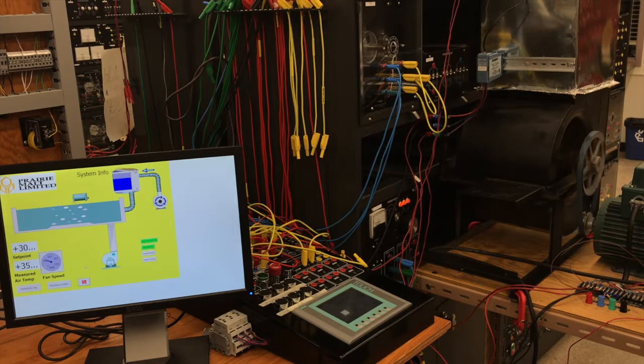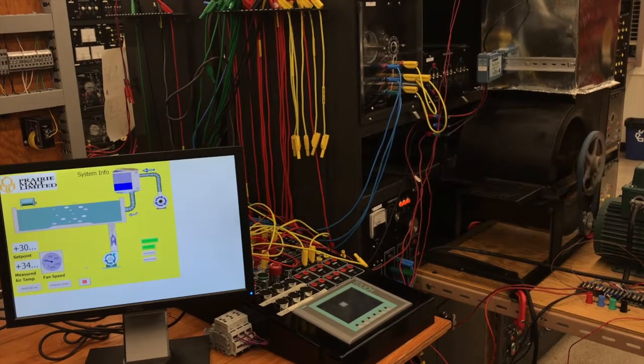This is the system screen, which shows what everything is up to, what's running and what's not. Currently it's just the fan, and the turner's going back and forth. On the plenum of the fan, you can see the Rosemount temperature transmitter. It's got a probe that runs up into the plenum, sits over top of the heater, and that's where we get our analog temperature signal back to the Scada system. It's a resistive temperature device which connects to the transmitter, and then the transmitter gives us an analog 4 to 20 milliamp signal back to the system.